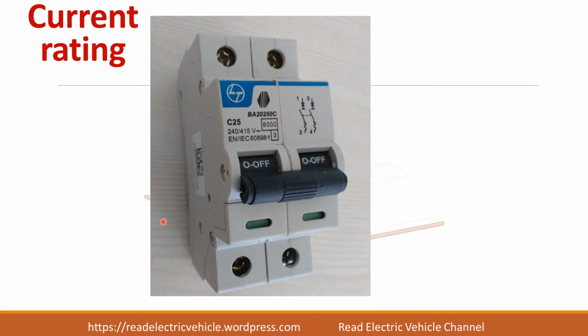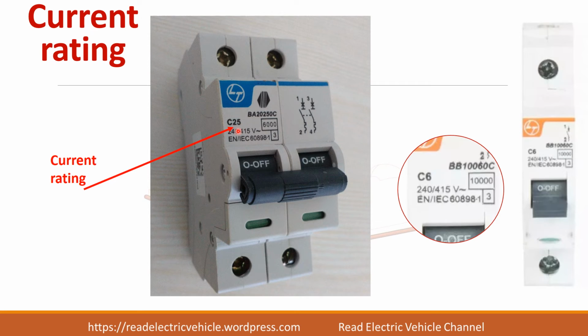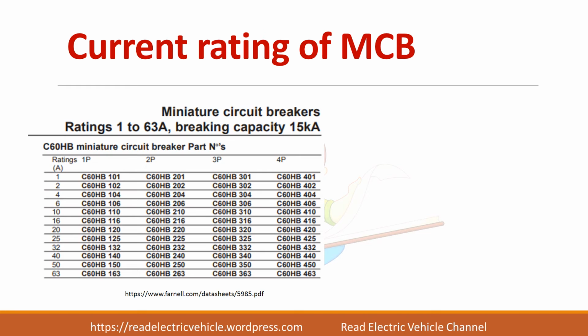Next we will see about the current rating. So here C25, we saw, is a current rating. So here you see C6 means it is a 6 amp MCB. Let us see about the available current ratings of MCB in the market. Mostly ratings from 1 amp to 63 amps are available. So you can see here these ranges are available. So it is available in all the 4 models, that is single pole, double pole, triple pole, as well as in 4 pole configuration.